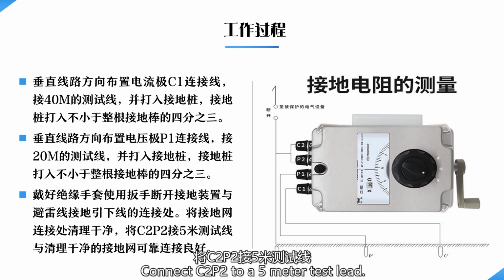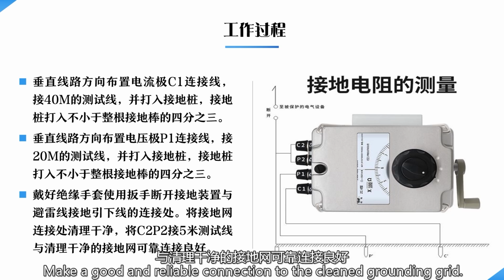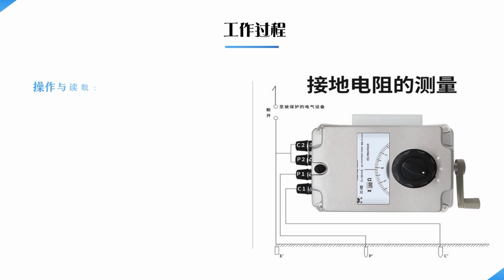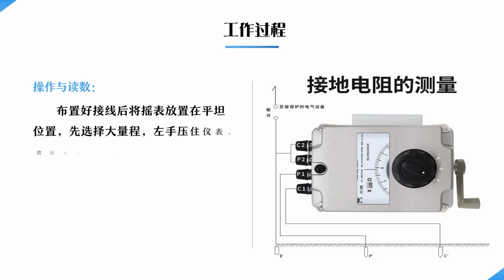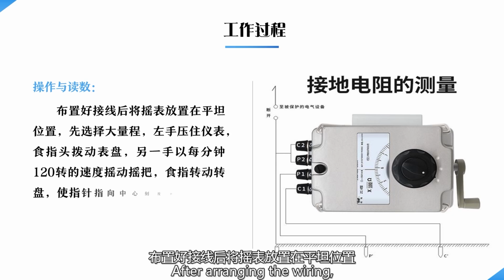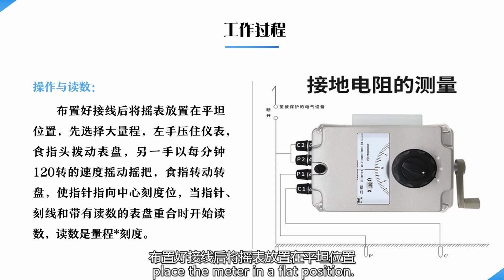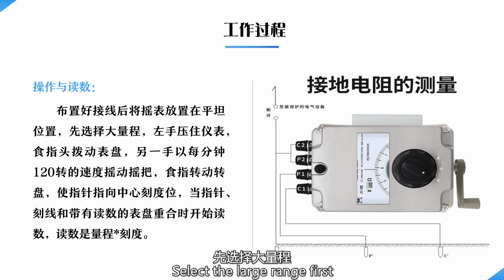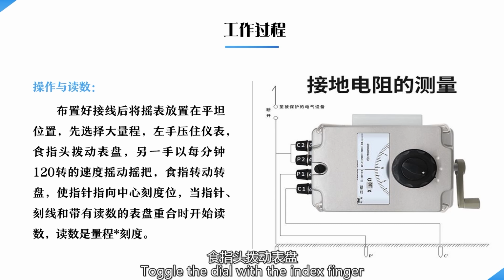Connect C2 and P2 to a 5-meter test lead. Make a good and reliable connection to the cleaned grounding grid. Operation and reading. After arranging the wiring, place the meter in a flat position. Select the large range first. Press the meter with your left hand. Toggle the dial with the index finger.